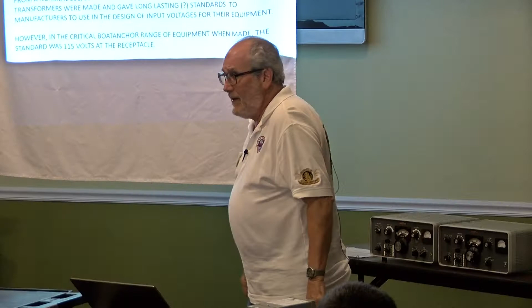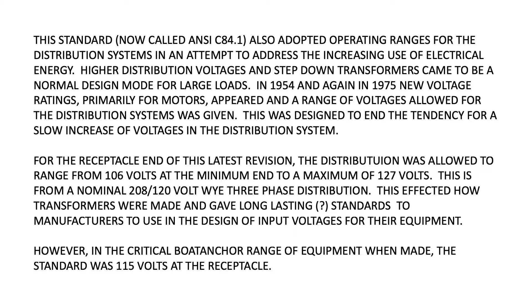For the receptacle end of the revisions, this is where we come in, the distribution was allowed, you need to read this along with me because you've got to grab hold of this, was allowed to range from 106 volts at the minimum to a maximum of 127 volts. Let's read that again. Was allowed to range from 106 volts to 127 volts. This is from a nominal 120/208 three-phase wye distribution system. This affected how transformers were made and gave long-lasting standards to the manufacturers to use in the design of input voltages for their equipment. However, in the Boatanchor range of equipment, the standard was 115 volts, and by golly, that's what they designed to. We want 115 volts in our equipment coming in, and if you do that, everything is fine.